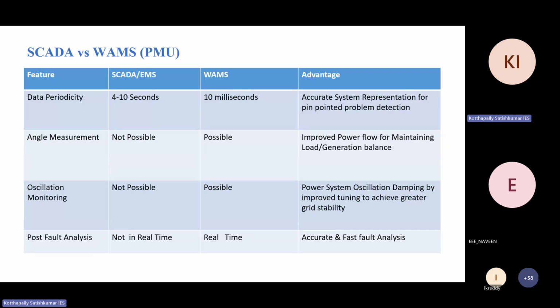So you cannot compare this data, and accordingly you cannot measure the phase angle between these two substations, because these two are captured at slightly different times. Within this difference of milliseconds, as you know, power system is a very dynamic system. Within this millisecond, the parameters will change, so it is not possible for you to measure this angle in the SCADA. Whereas you can with the PMU. Now I will tell in the next slides exactly how we measure the phase angle, which is not possible in SCADA, and how it is possible in PMU technology.